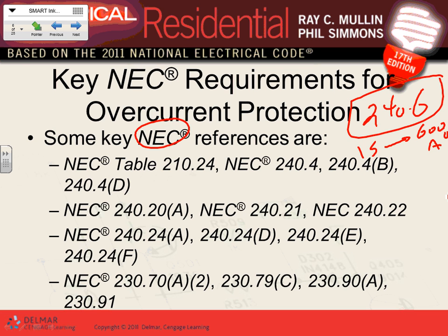When you have a circuit breaker, guys, it has to have the voltage on it. Number one, is it single phase or three phase? Number two, how many poles? Is it one pole, two pole, or three pole? Number three, the maximum voltage. Is it 600 volt or 300 volt that you can put on this? If it's 600 volt, you can put all the voltages on it. So if I have a 600 volt circuit breaker, guys, can I tie a 208 system to it? No problem, because it fits, right? 600 volt is the maximum voltage. So they have a voltage, and they also have an interrupting rating attached. So you have to have an interrupting rating, like this one says 10,000.